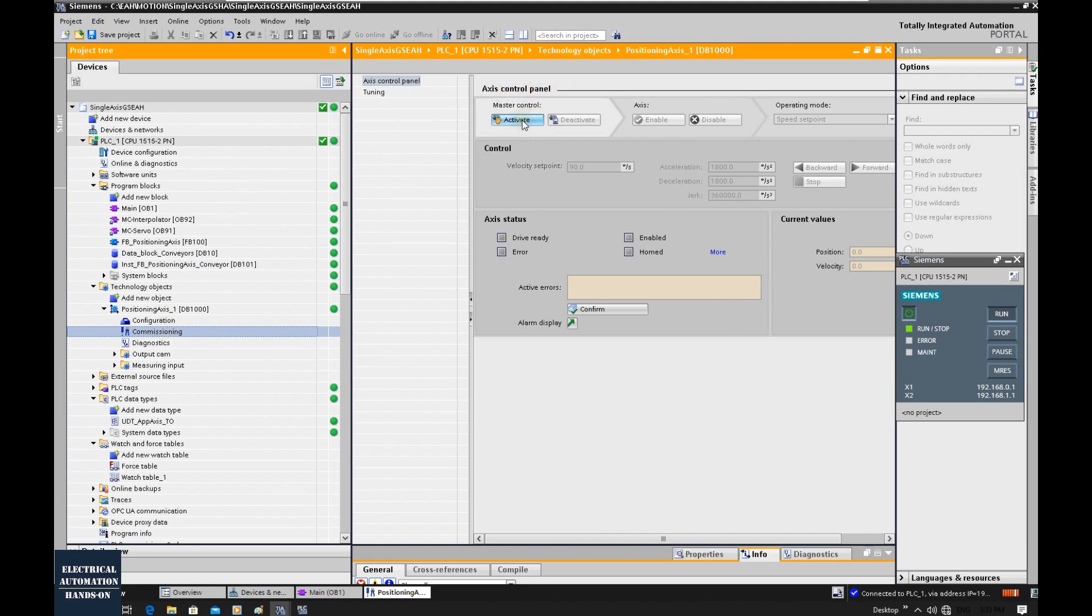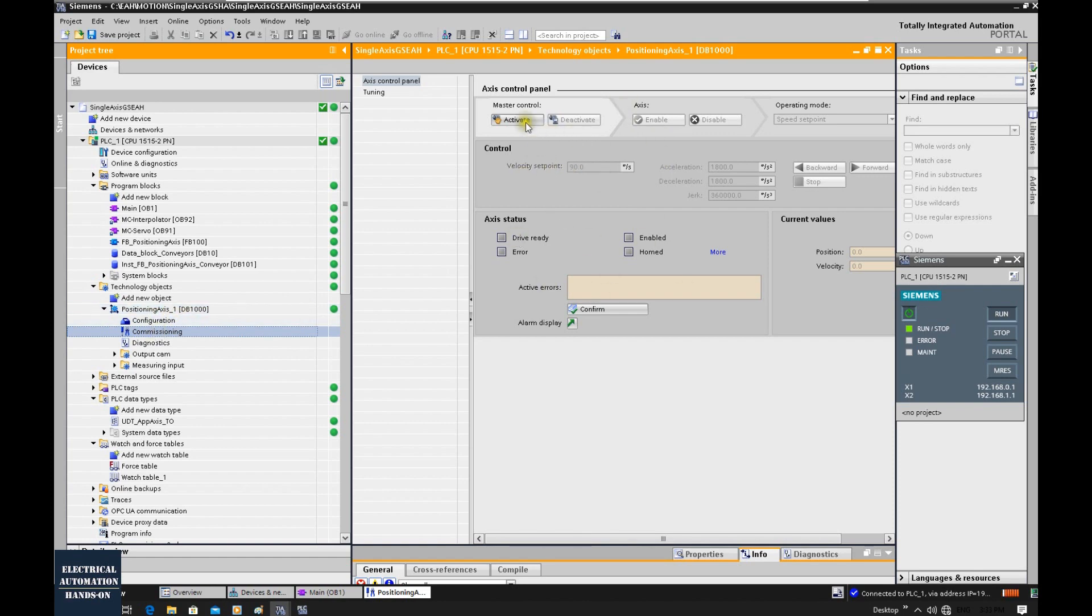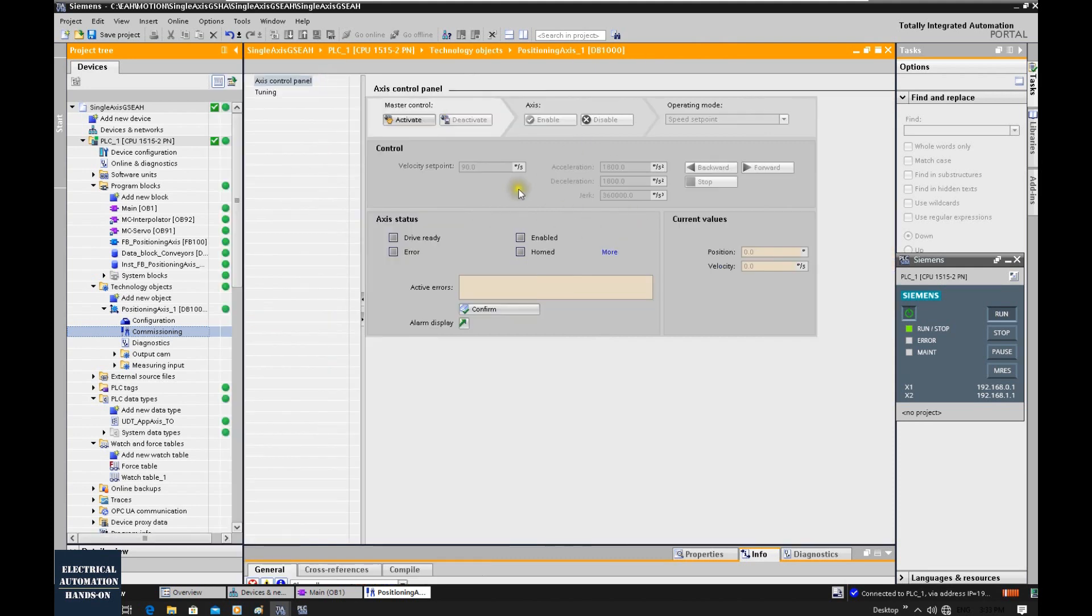Once we activate this master control, the logic will be bypassed. Your motion control is now under this axis, so this axis will be fully controlled by this panel only. Your program will be bypassed. Using this way, we can set a slow speed and verify the direction, and verify if the motor can actually drive our load properly or correctly.